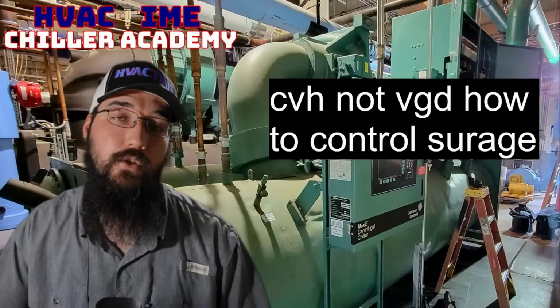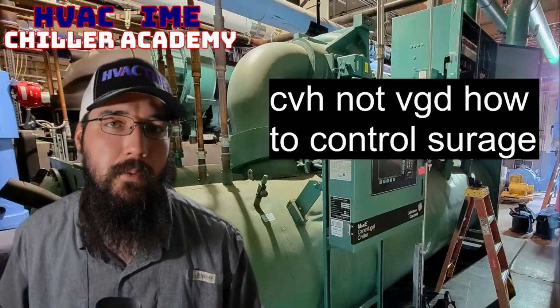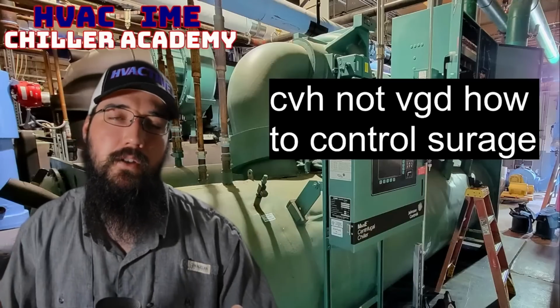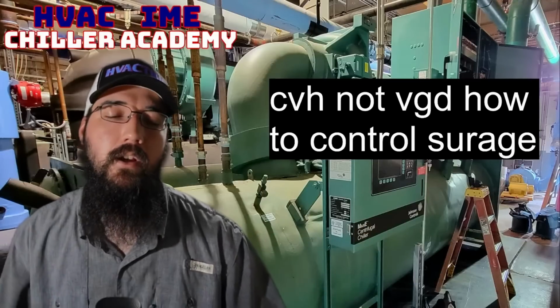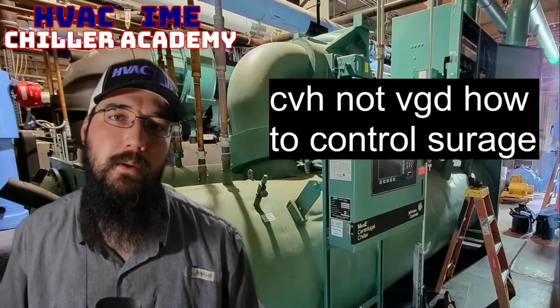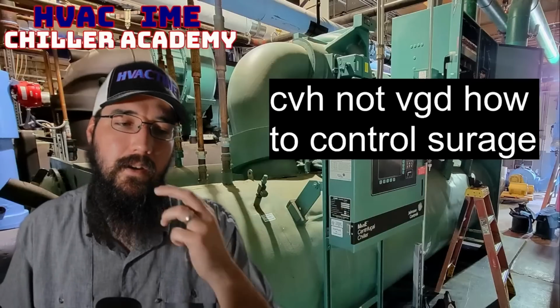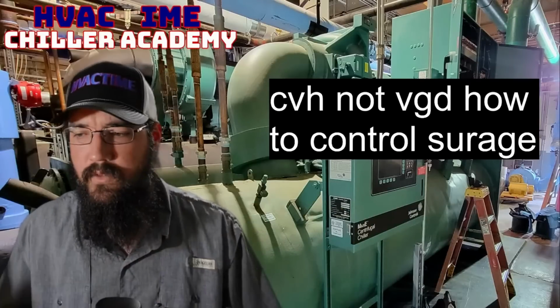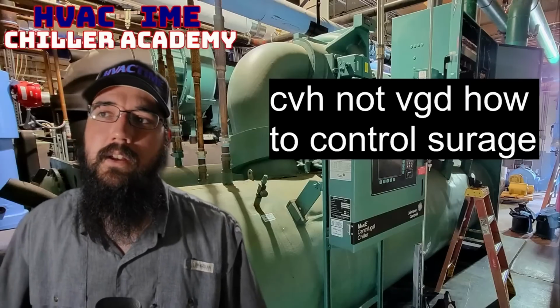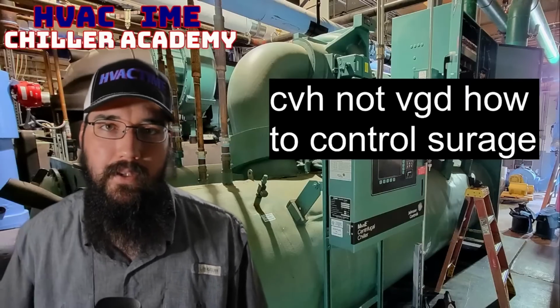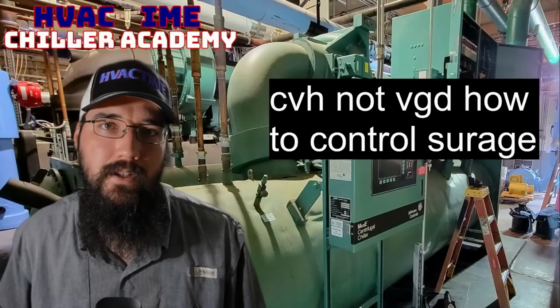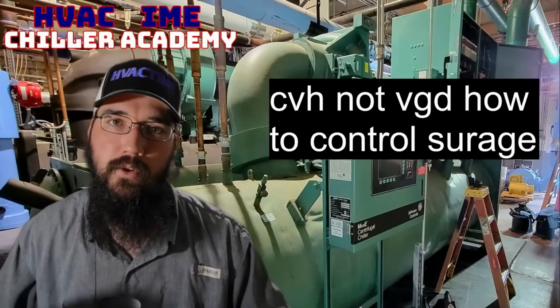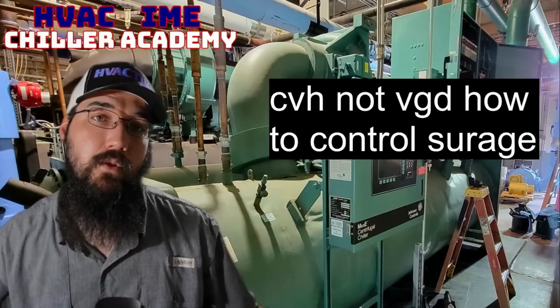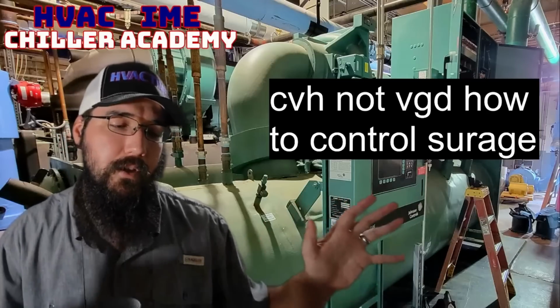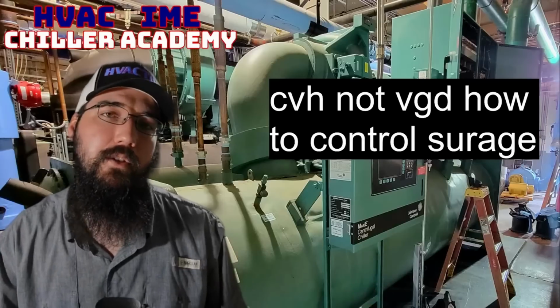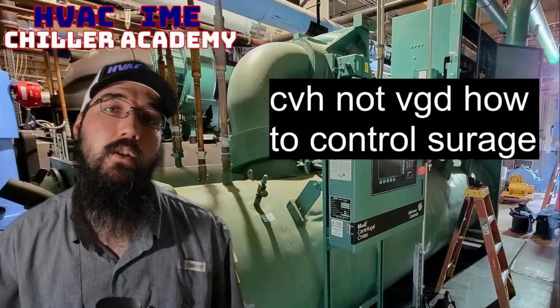Now, the second way to do this would be just raising your chill water set point, because again, all of this goes around the theme of we got to get the lift down. So raising that chill water set point can help do that. If you don't want to use current limiting, you're trying to run a 45-degree leaving water, then just take it to 48 or 50. I've had plants that were poorly designed and don't have proper flow control. And so we would have to run, it's basically a reset, but we'd have to run a 48 to 50 degree leaving water in the winter time or in the lower load seasons.